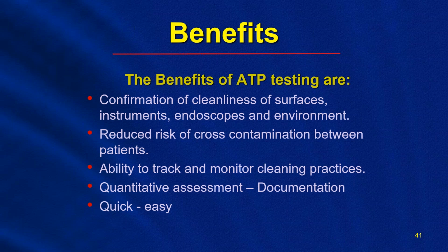So the devices can actually be used to program certain things. So an example would be, say in the GI suite, they may want to label or program it for endoscope number 1, 2, 3, 4, and 5. And for some reason, every time they clean and test the scopes, number 5 seems to be having an issue. Well, that may mean that number 5 scope should go out for repair or testing to see if there's any compromise going on that they're not aware of. Or what about cleaning practices? If in Central Sterile, they're going to check the cleaning practices of John, Jane, and Joe, and for some reason, Joe's having more higher levels of ATP when he does instruments, maybe that could indicate he needs to be retrained.